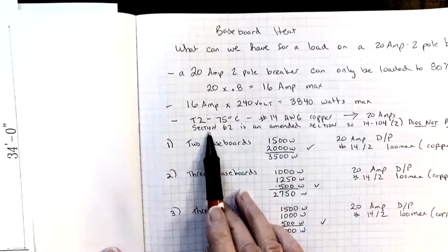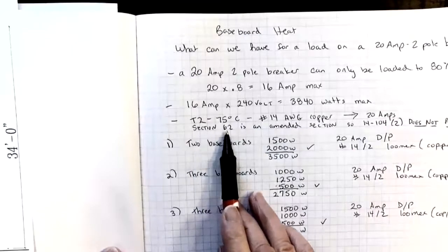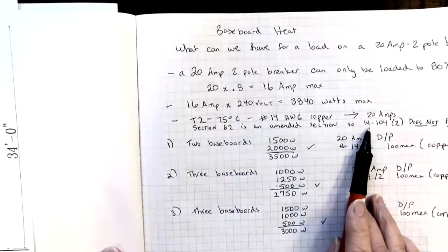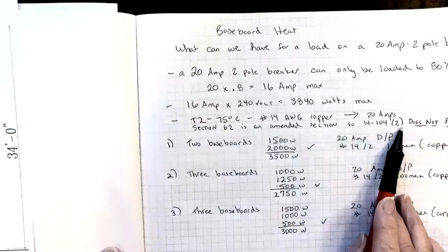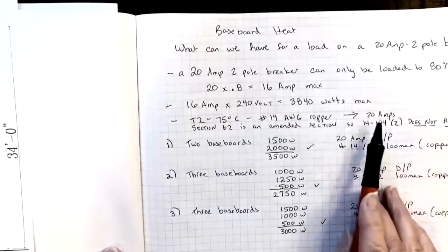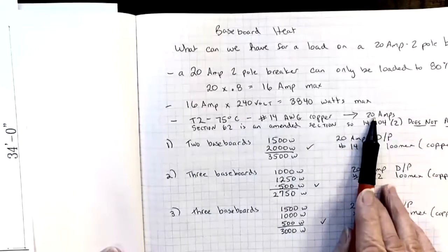In a previous video I talked about what an amended section means. Section 62 is an amended section. So that means that the rule in 14-104 does not apply. In other words, we can put a 20 amp breaker on this number 14 copper wire.